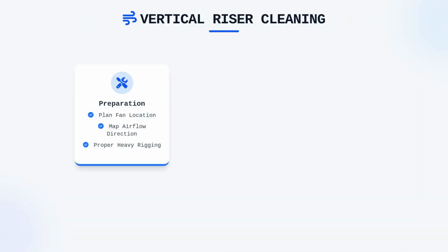The physical act of cleaning vertical risers requires careful planning regarding the location of the exhaust fan and the direction of the airflow. Most roof-mounted fans are heavy and require proper rigging, especially if you need to gain access to the discharge point for a top-down cleaning approach.